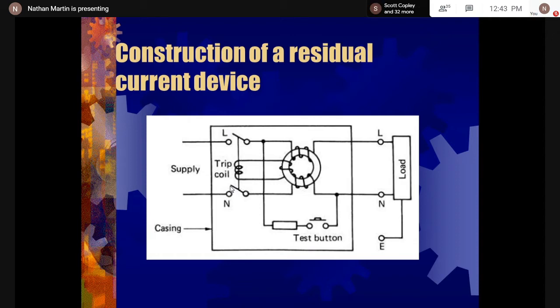So it's a simple circuit, guys, but very effective. And you realize because of how the circuit is designed, the small change in these two current values, that's a line current and a neutral current, right? The device will trip, before it becomes dangerous to the point that you are exposed to probably a touch potential, right? The device will trip and trip out the circuit.